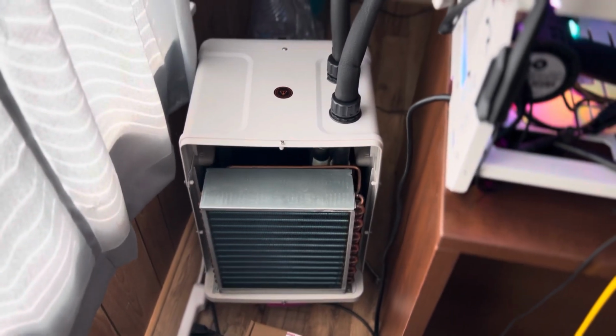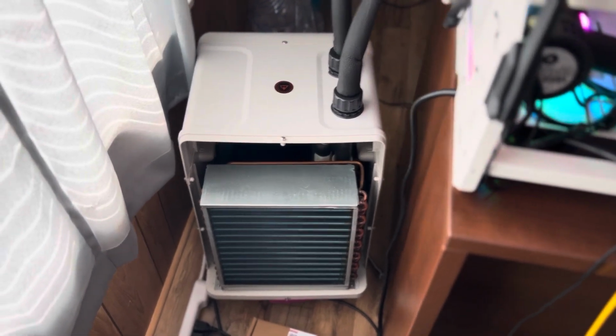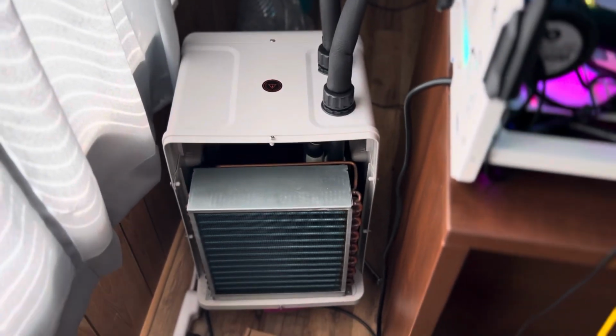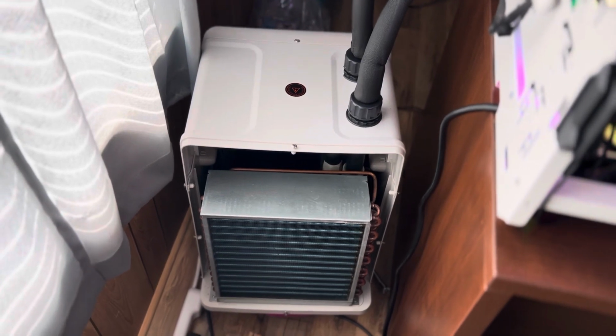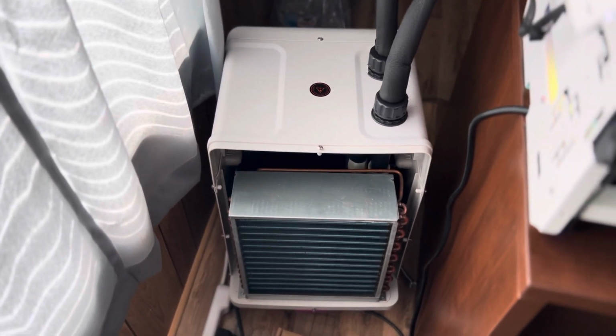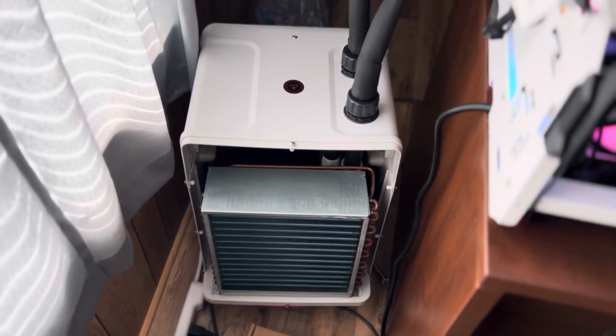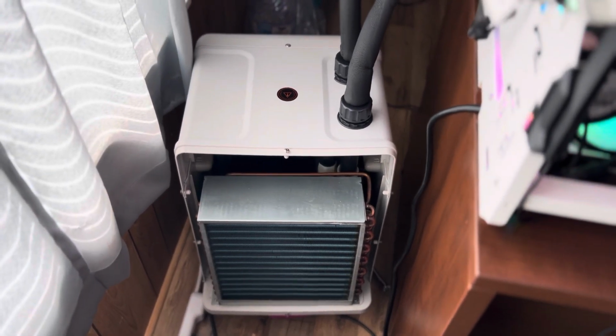The buffer tank is 10 gallons, and the reason I went with 10 gallons is because apparently if you're after water accuracy for the temperature, you want to go over 6 gallons. 6 to 10 gallons or more, depending on what you're cooling, of course.